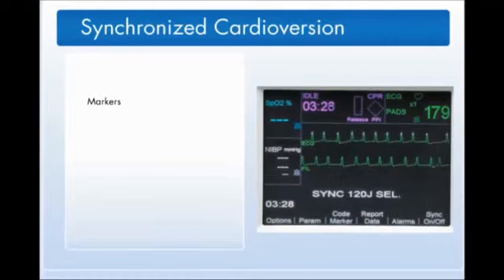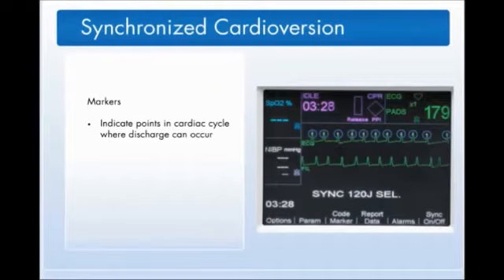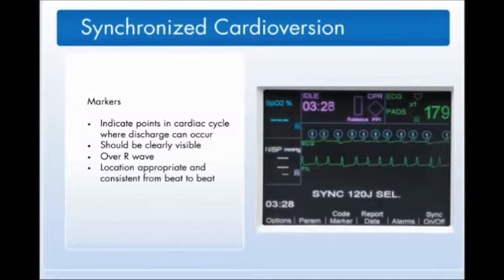Once in sync mode, the device displays markers, the down arrows, above the ECG trace. These markers indicate points in the cardiac cycle where discharge can occur. Verify that the markers are clearly visible on the monitor and that they are over the R wave, and that their location is appropriate and consistent from beat to beat. If necessary, use the lead and size buttons to establish settings that yield the best display.